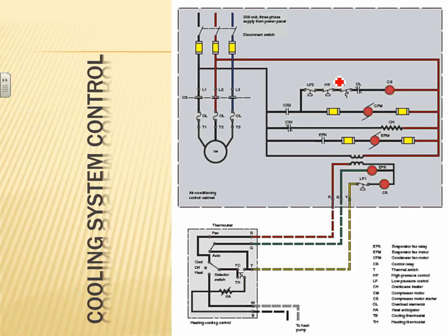Okay, then I went into something about controls. This is a very simple control system, guys, for a three-phase AC unit with a compressor. I don't know how clear that one is. I have my controller, my thermostat, in here. These wires are a so-called Class 2 circuit that I believe the mechanical contractors will be picking up, but you have to ask about these. It's Class 2 circuit thermostat wire going between your thermostat and your compressor.